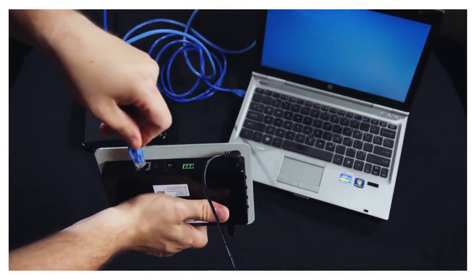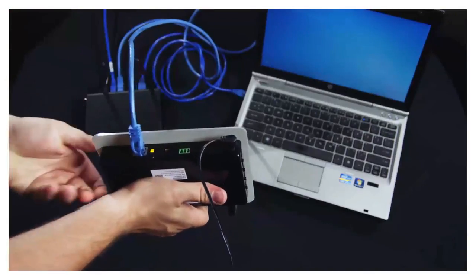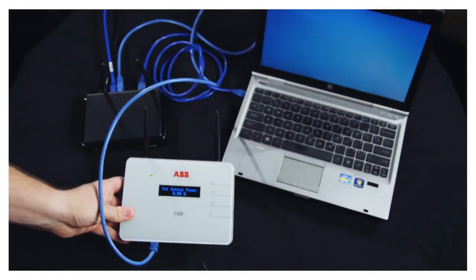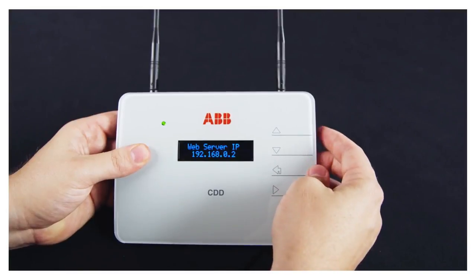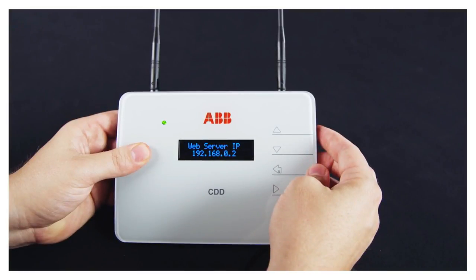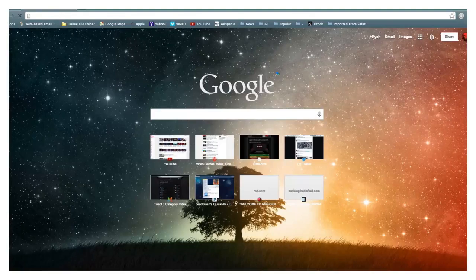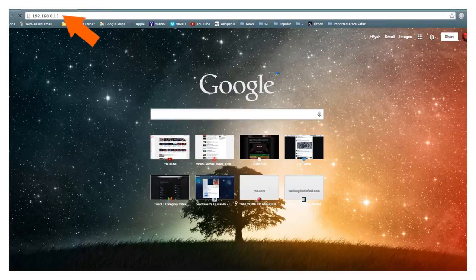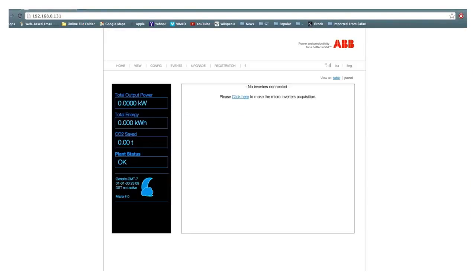For the purposes of this video, I will be using the Ethernet connection to acquire the ABB microinverters. Once the CDD is connected to the network, press the Escape key to display the IP address for the CDD. Note that this IP address may change depending on the type of network the CDD is connected to. Open a web browser on a computer, smartphone, or tablet. In the address bar, enter the IP address displayed on the screen of the CDD. This will open the CDD web server interface.